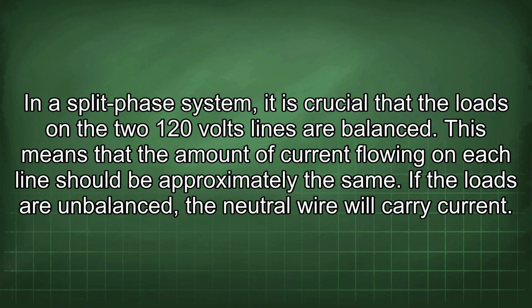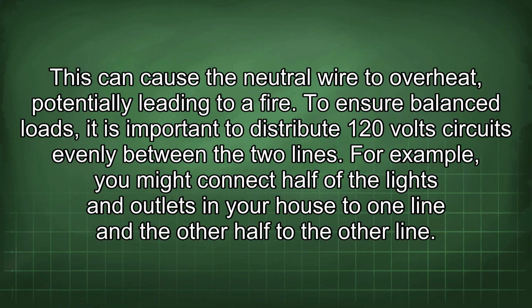In a split-phase system, it is crucial that the loads on the two 120 volt lines are balanced. This means that the amount of current flowing on each line should be approximately the same. If the loads are unbalanced, the neutral wire will carry current. This can cause the neutral wire to overheat, potentially leading to a fire.